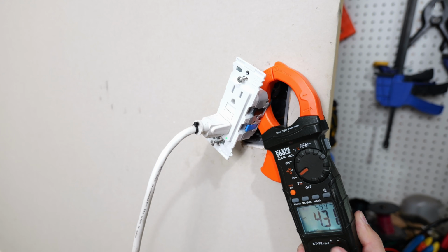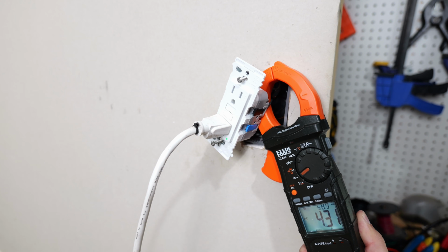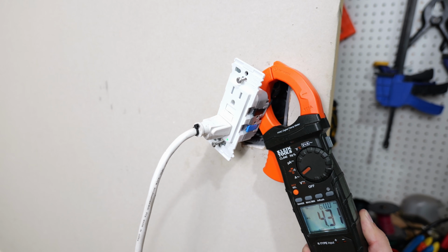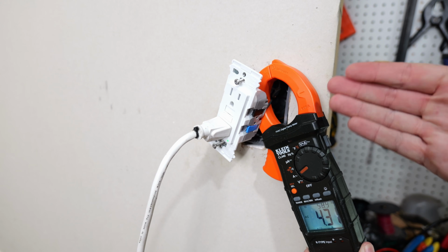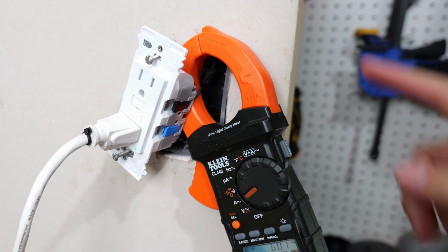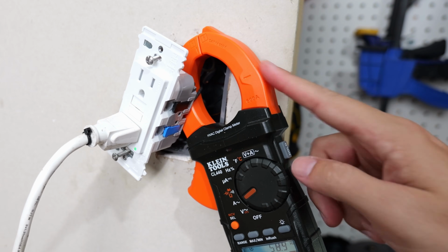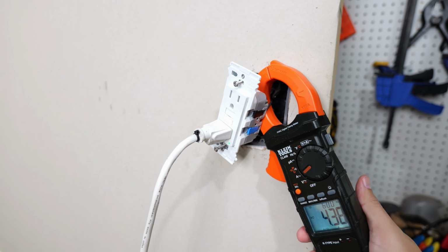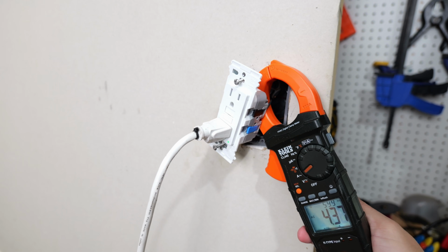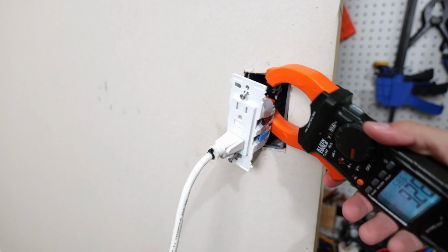So that's one way to get your amperage reading on whatever you're wanting to test. Just pull the outlet out away from the wall, put the clamp around the feed wire, and you're going to get your amperage reading. I was never in danger of touching anything hot here because I was able to just use the plastic clamp to wrap it around the wire. I wasn't messing with any probes, and my hands really didn't need to get anywhere near it. So that's one way.